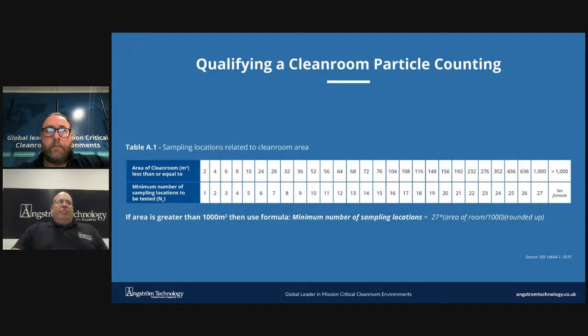What you can see here is the table within the ISO 14644 Part 1 standard, which illustrates the number of particle counting locations in relation to the area of the room. The engineer will measure the room area, and using table A.1 will look up the number of locations required to sample. For example, a room with an area of 10 meters squared would require 5 locations. A room 15 meters squared is situated between the 10 and 24 meter squared boundaries, and therefore the engineer should select the higher amount of locations, in this example 6 locations.